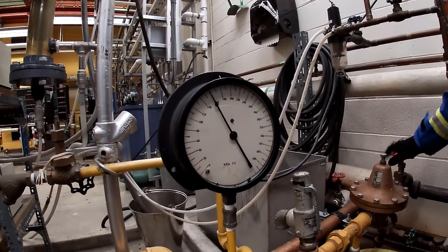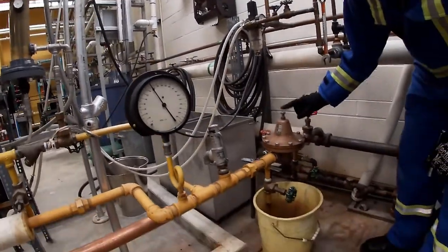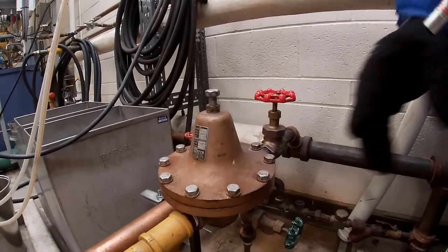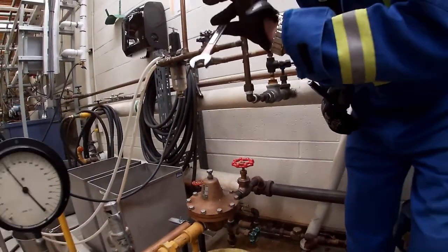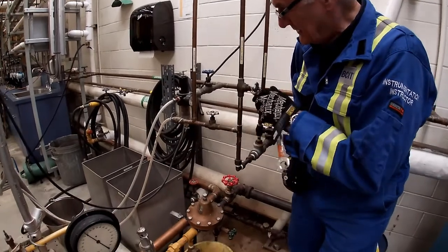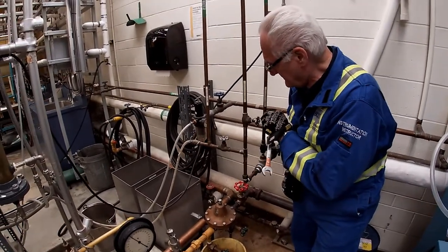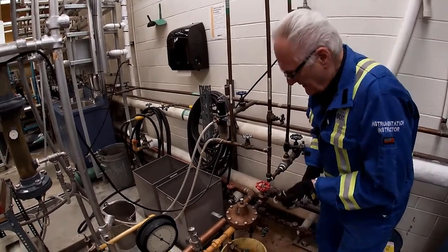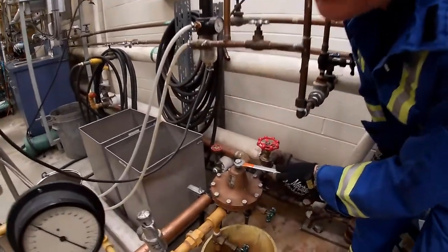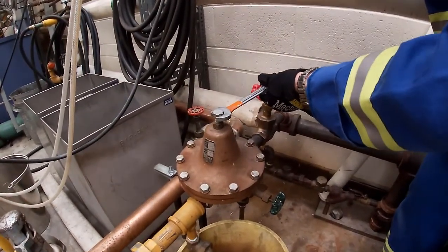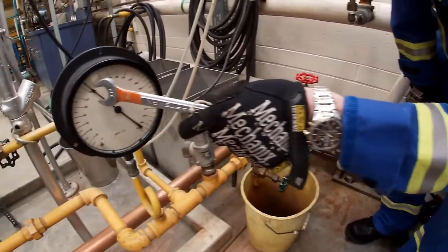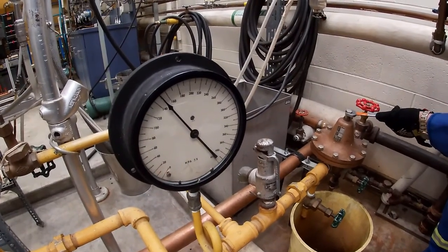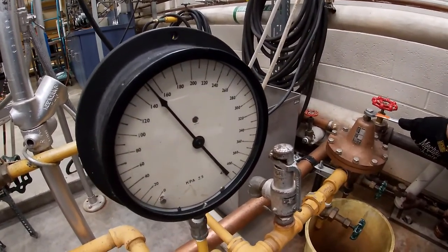Now, if we need to raise or lower this pressure, there's an adjuster on this spring right here, and there's a spring underneath so that the regulator will set the pressure. This wrench stays hanging here, because if you need to adjust that, you're going to take it off of here. Gloves don't help. Then you would either lower the pressure. You can see I've turned it counterclockwise, and now the pressure's dropped to about 153, 154. I'm going to bring it back up to, I hope, 160.